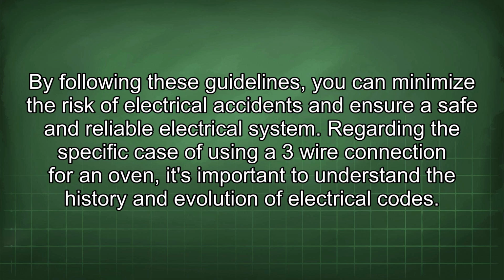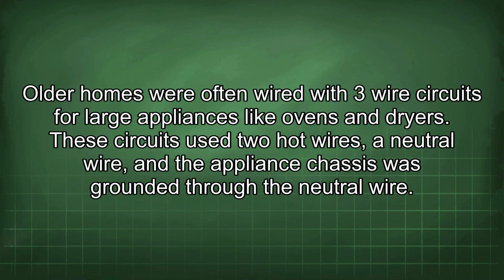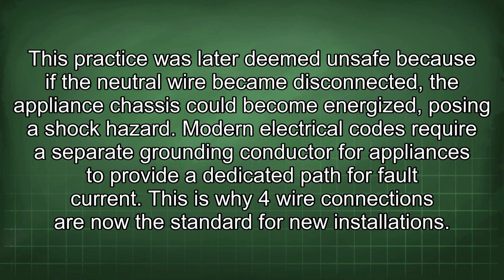Regarding the specific case of using a 3-wire connection for an oven, it's important to understand the history and evolution of electrical codes. Older homes were often wired with 3-wire circuits for large appliances like ovens and dryers. These circuits used 2 hot wires, a neutral wire, and the appliance chassis was grounded through the neutral wire. This practice was later deemed unsafe because if the neutral wire became disconnected, the appliance chassis could become energized, posing a shock hazard. Modern electrical codes require a separate grounding conductor for appliances to provide a dedicated path for fault current. This is why 4-wire connections are now the standard for new installations.